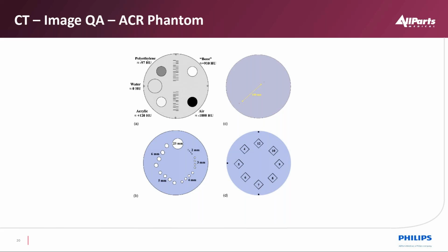There's a spec for this phantom as well. It's plus or minus a few CT numbers that we would expect with our certification of the phantom. And then there's usually a hole in the phantom that represents air. The lines that you see would be representative of different line pairs, as far as 1 millimeter, 2 millimeter, 5, 10, so that we see the full depth of that.